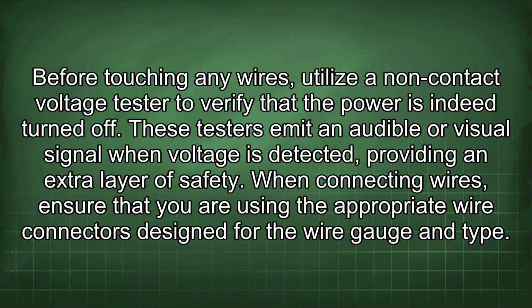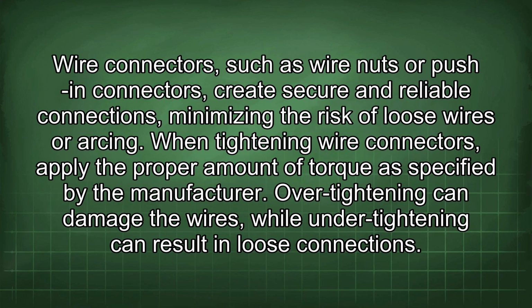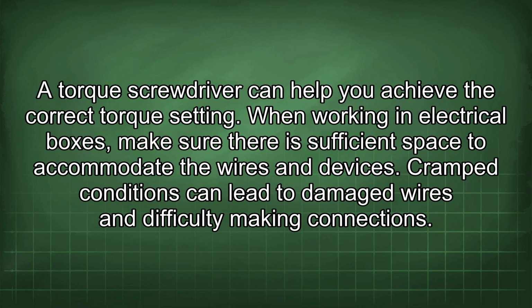When connecting wires, ensure that you are using the appropriate wire connectors designed for the wire gauge and type. Wire connectors, such as wire nuts or push-in connectors, create secure and reliable connections, minimizing the risk of loose wires or arcing. When tightening wire connectors, apply the proper amount of torque as specified by the manufacturer. Over-tightening can damage the wires, while under-tightening can result in loose connections. A torque screwdriver can help you achieve the correct torque setting.